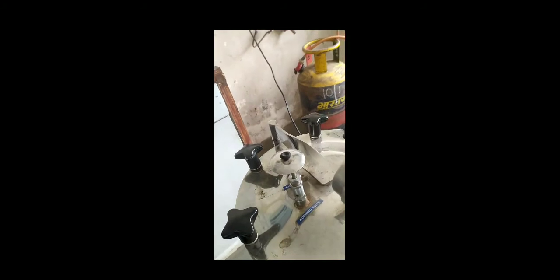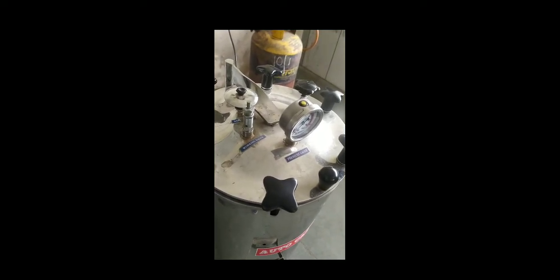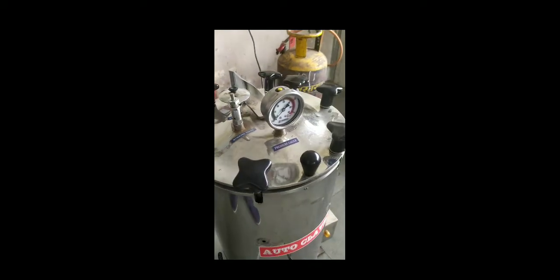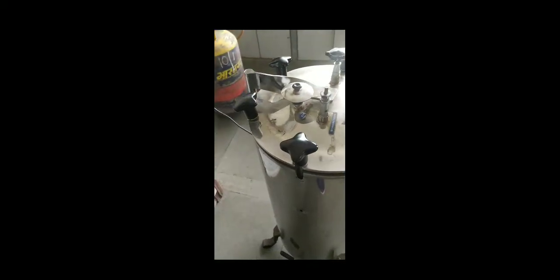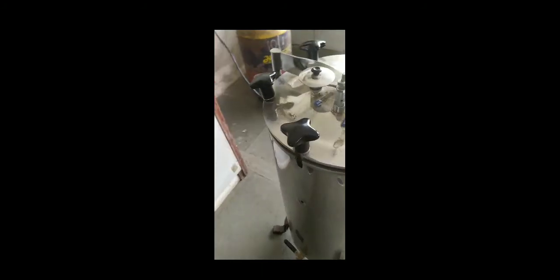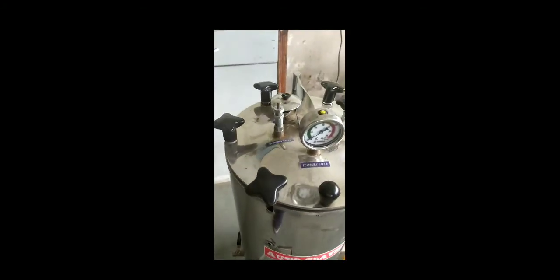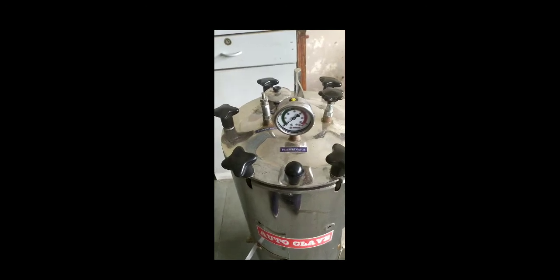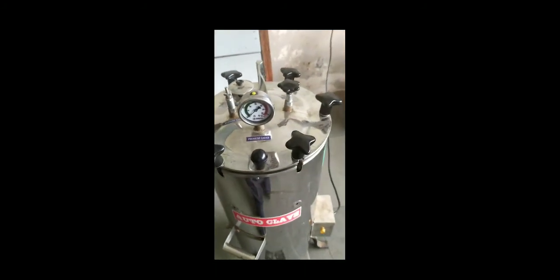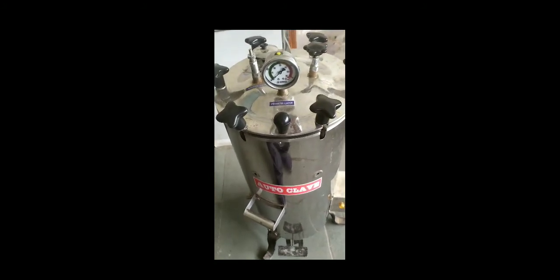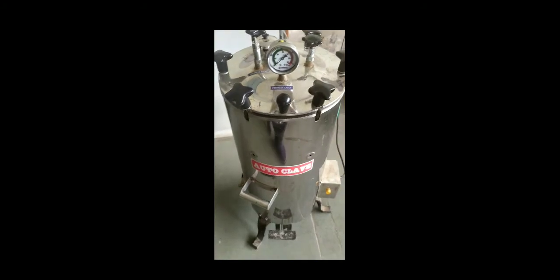After tightly closing this air vent, the time depends on various time spans. The ideal statistics for the autoclave are 15 lbs pressure at 121 degrees Celsius for 30 minutes. This is the ideal temperature and pressure for the autoclave to work and sterilize. After sterilization, you have to check that the pressure has completely gone down to zero. After that, open the vent so the remaining pressure or vapor escapes from the autoclave. Then open the lid and remove your products from the autoclave. This is the autoclave.